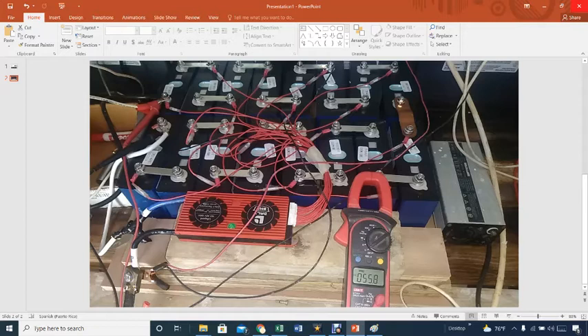Right now the battery is showing 55.8 volts, about 56, and it's a very sunny day, which is why it cut off the charging process. Typically it cuts off at 55, but that's perfect. I've been monitoring this for several weeks, and it's always about 55.7 to 55.8. The cutoff stops it from charging more, but the batteries are in good shape.